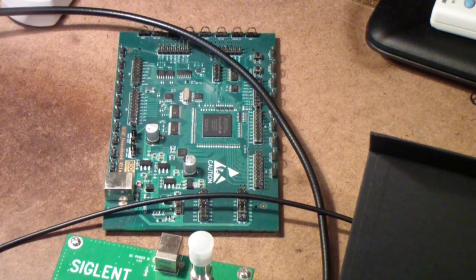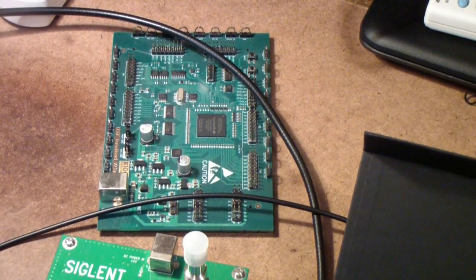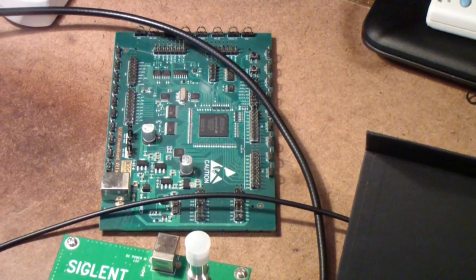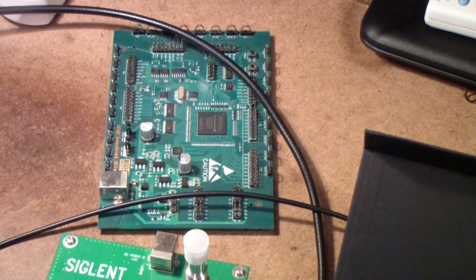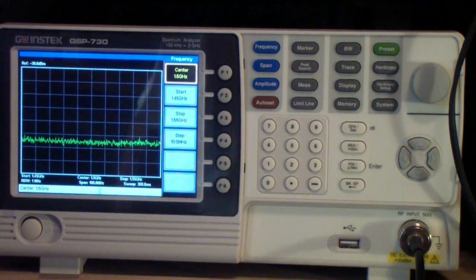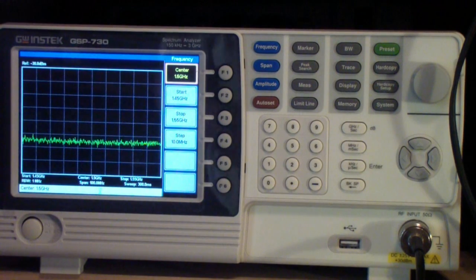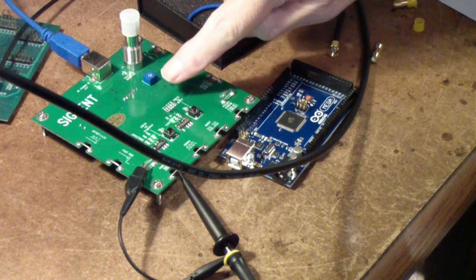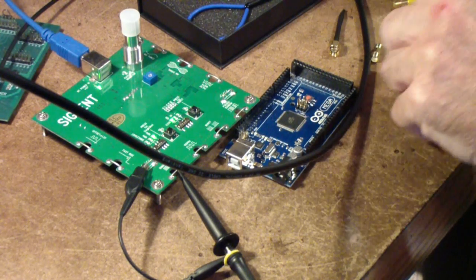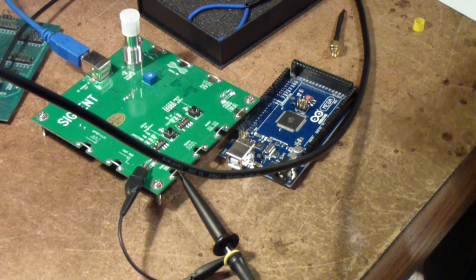I'm going to try to show these probes in use both with spectrum analyzers and with oscilloscopes. The first thing I'm going to do is to use this Instek GSP-730 spectrum analyzer. It goes up to about 3 gigahertz. And by the way, I'll show you the specs on these Triarchy probes in a little bit. I've connected up this Siglent board to a USB connection, actually just to a USB power supply.